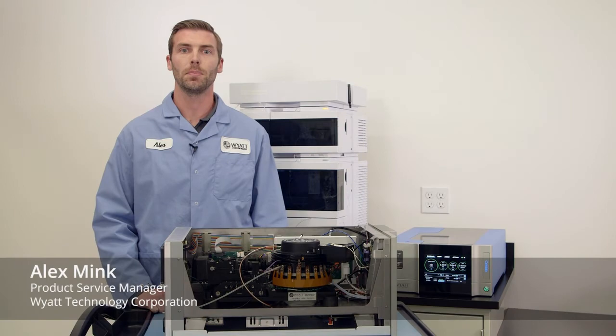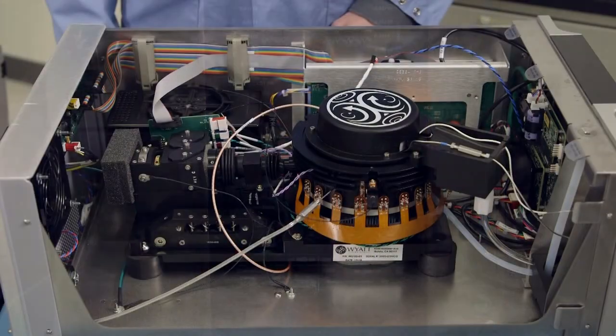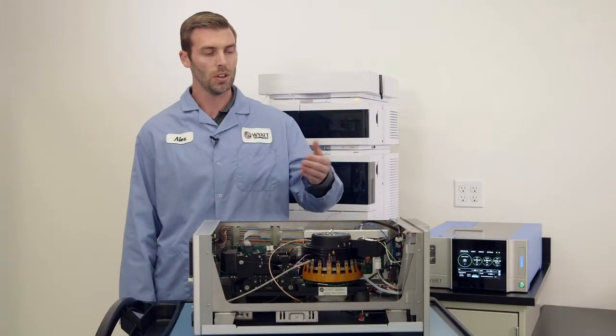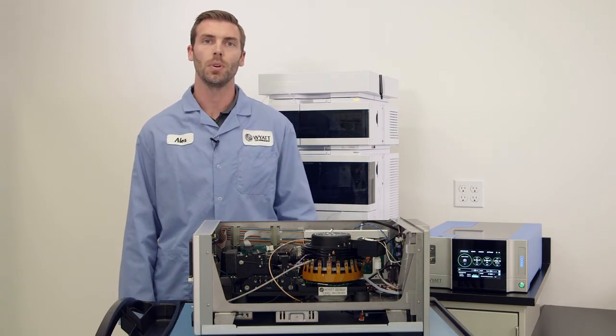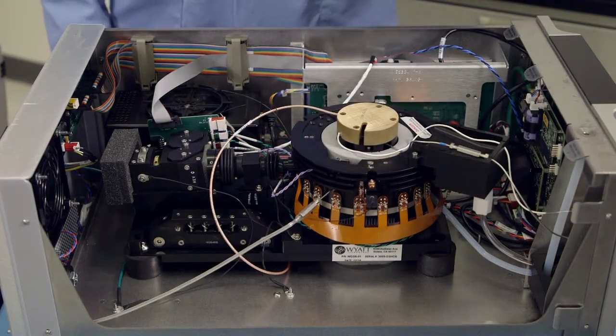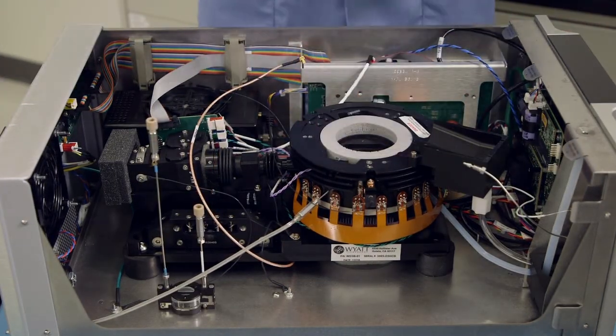Hello everyone, I'm Alex Mink, and I would like to point out some additional convenience features that help make owning a Wyatt instrument effortless. Our inline DLS WyattQELS is very modular and can simply be added in the field. You can also move the QELS detection angle at any time, and our software will auto-identify and adjust accordingly. With our advancements in flow cell technology, we have created the first ever field-replaceable flow cell.